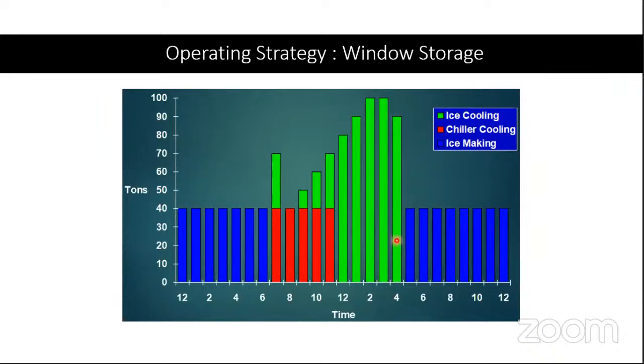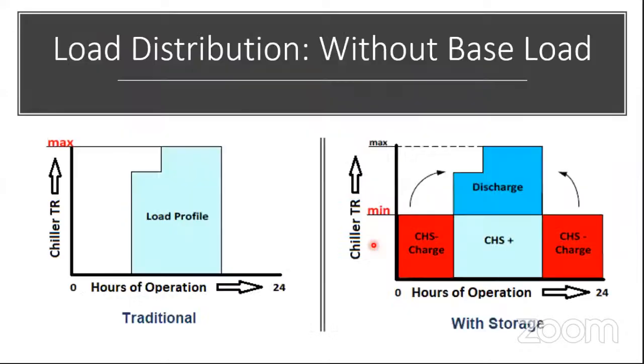Let's say there is a power cut, and it is planned that for these five hours I'm going to have a power cut at my site, and I better not use chillers. I might want to use thermal storage only to save on my DG cost. Or there could also be a case that for these 5 hours, my tariff was very high. So I prefer not to use chillers during these hours, and I prefer using storage instead. So this is also possible, window storage. Based on that, we develop our load distribution profile.